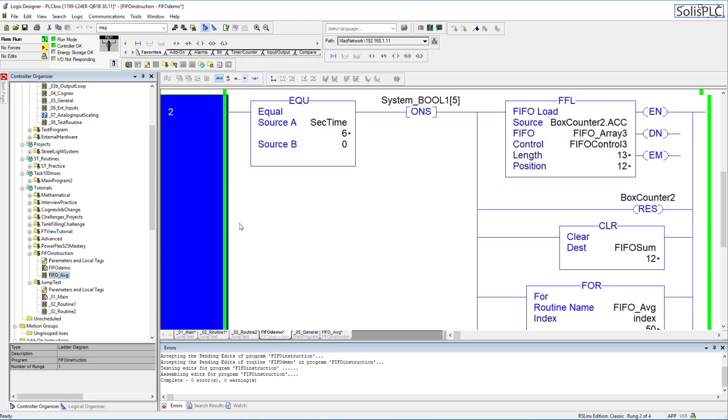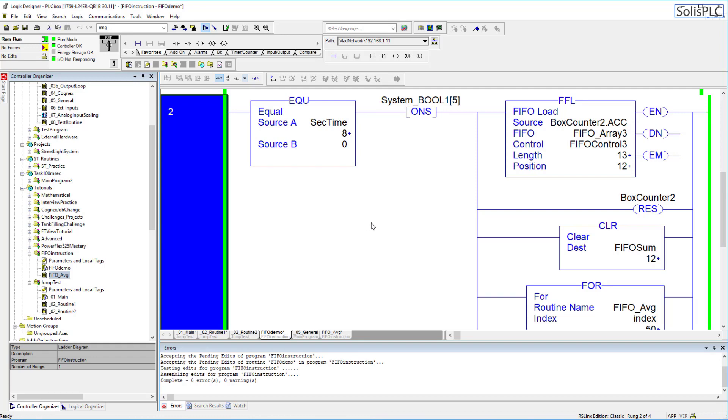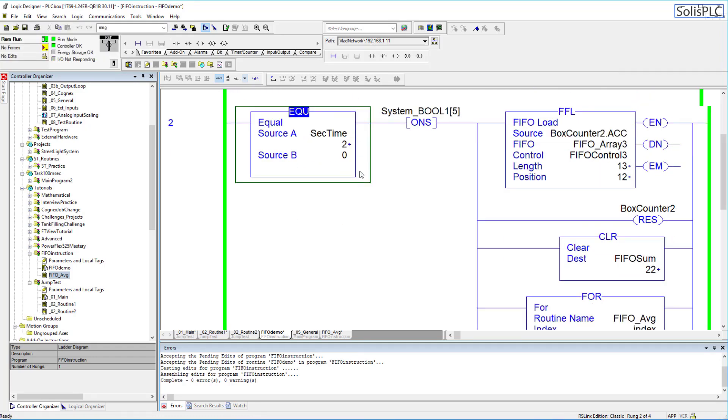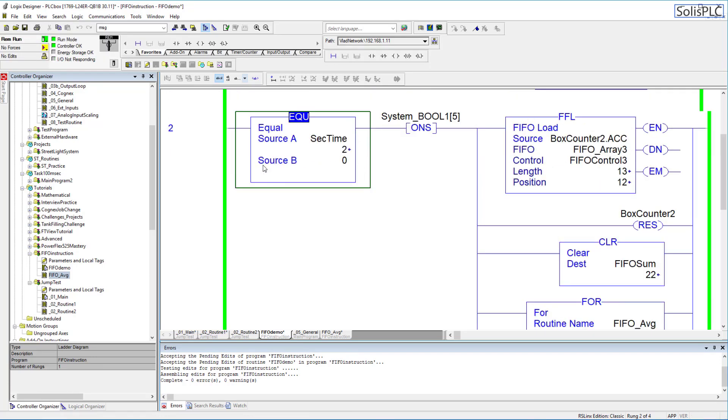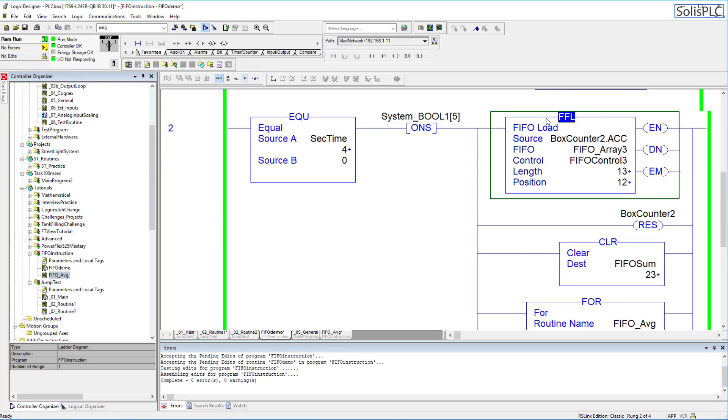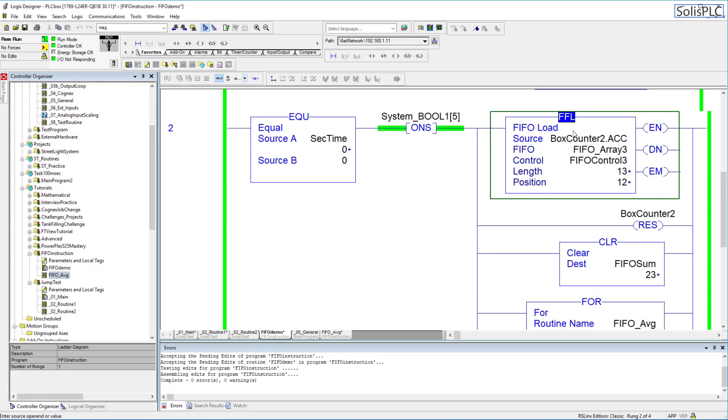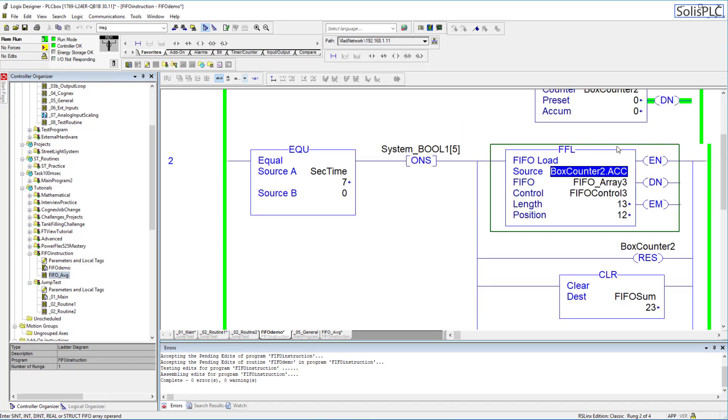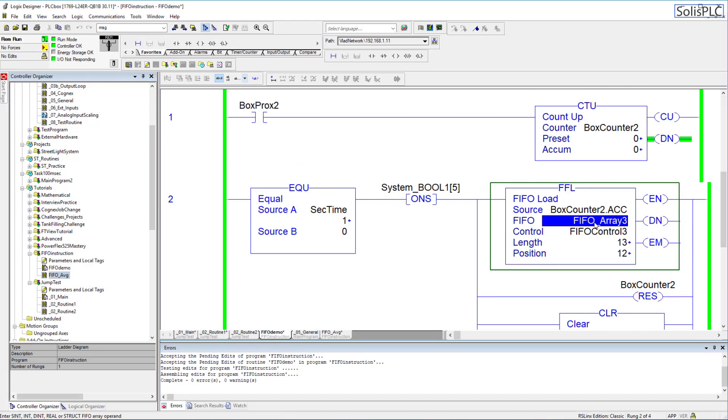How do we capture the number of cases created? This is where it happens. First of all, I'm looking at the timer to be at zero seconds. So every 10 seconds the counter for seconds is going to be reset to zero, and at that point I have a one-shot which goes into this FIFO load instruction. This is a very, very important instruction that you should be familiar with. What the FIFO load does is it takes the counter value, so the number of cases counted by this box counter, and it shifts it into this FIFO array.